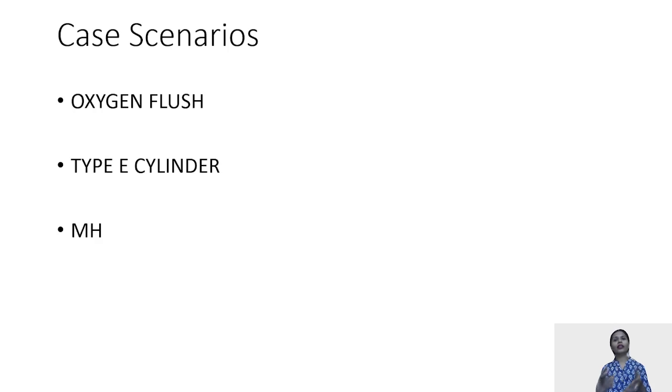So tank factor into the pressure of the type E cylinder, which per se is 2000 psi, but you can see that on the pressure gauges also, if practically you have to see it, upon how much oxygen flow has been opened. That is your type E cylinder, this much amount of oxygen it can deliver.